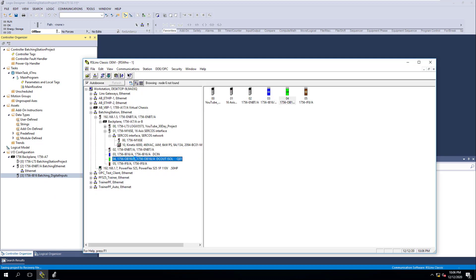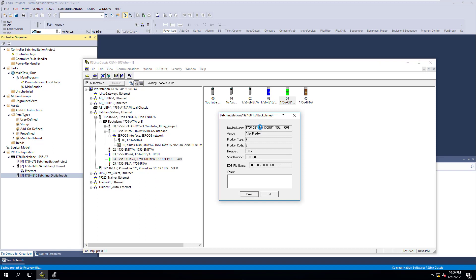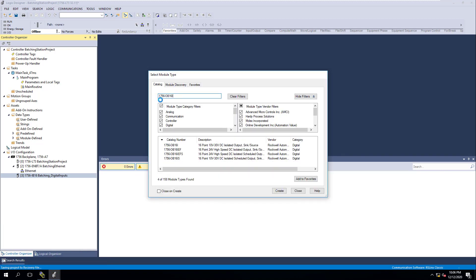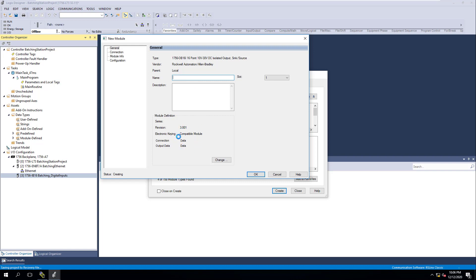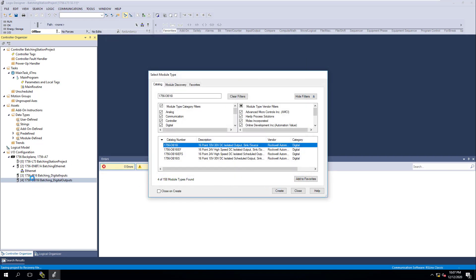Now we're going to add our outputs. We right-click and the specific card we have is a 1756-OB16I — that's just an isolated DC output. The firmware version is 3.002, so we add that in, paste it in here. It's a 10-to-30 volt DC isolated output. The version came in correct so we're good. We set compatibility, this is slot 4, and we'll call this 'batching digital outputs'. That gives you a firm understanding of what we're putting in. We have our digital inputs, digital outputs, and Ethernet so far.